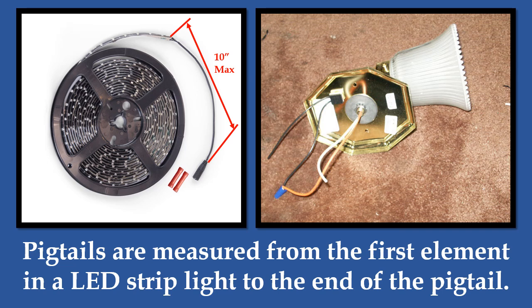Again, the maximum length of a small gauge pigtail must be less than 10 inches, or the overcurrent protection for the entire length of the pigtail must be appropriately sized. Any pigtail longer than 10 inches must be fused according to the pigtail's wire gauge size. If the pigtail supplied with the lighting or other utilization device is the same gauge as the wire connecting with the 12 volt power, the overall length of the pigtail does not present an overcurrent hazard.